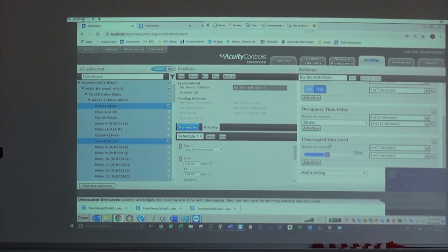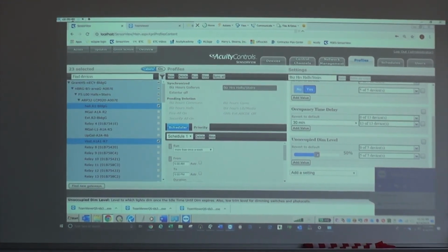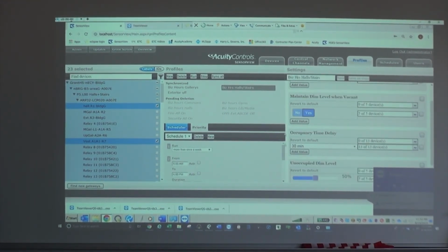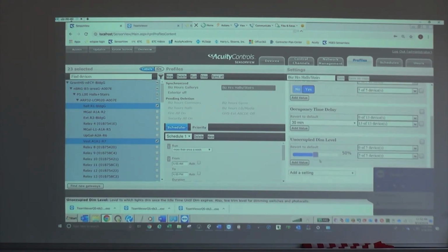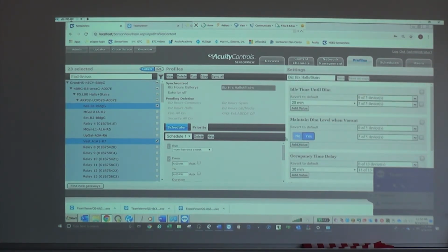The unoccupied dim level is set to 50%. So we've changed the occupancy time delay to 30 minutes from 15, and changed the unoccupied dim level to 50%, stopping it from turning off because we want to maintain it at 50% even if unoccupied during business hours.